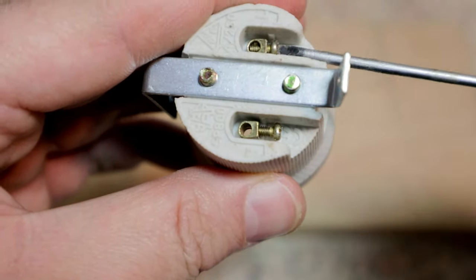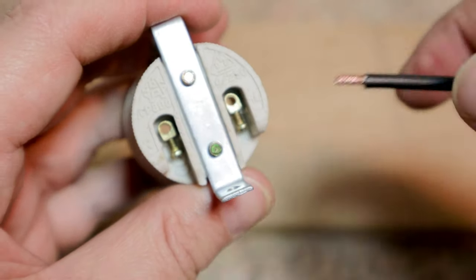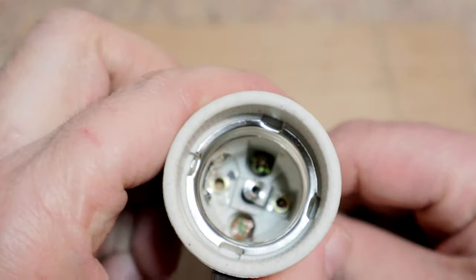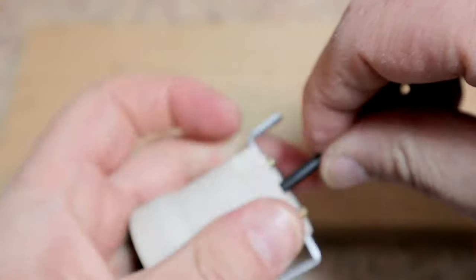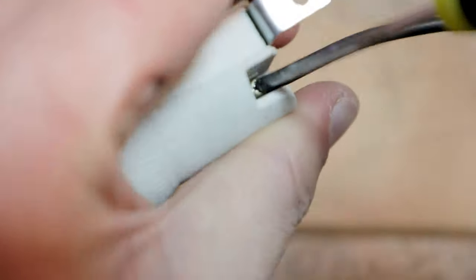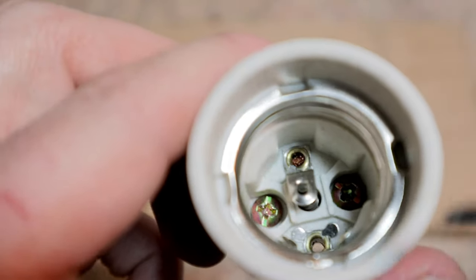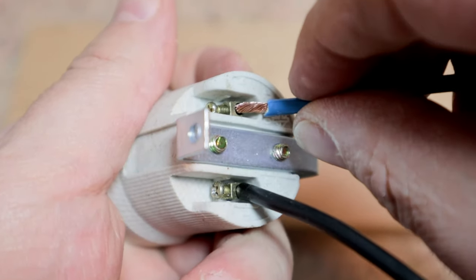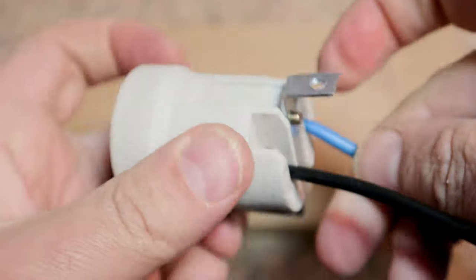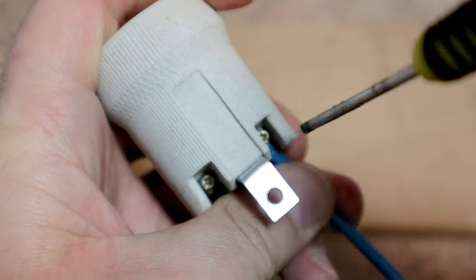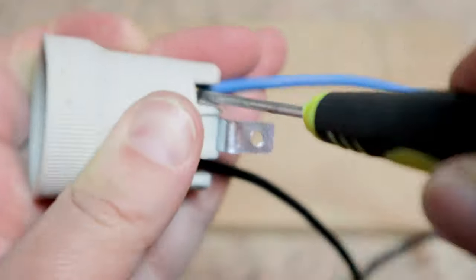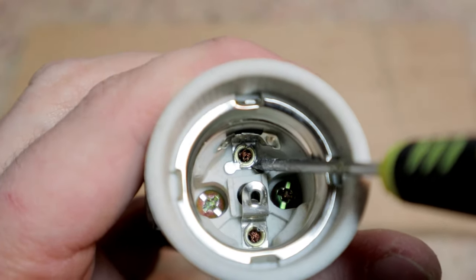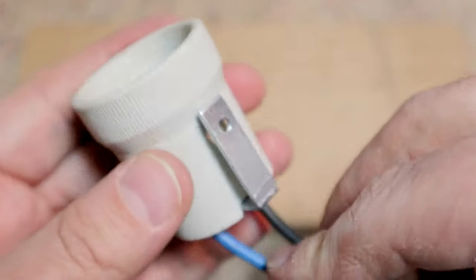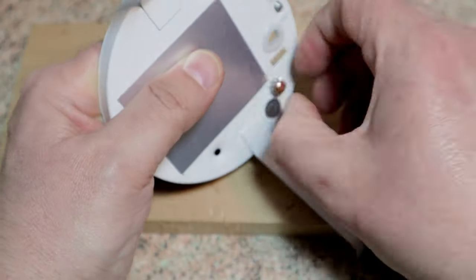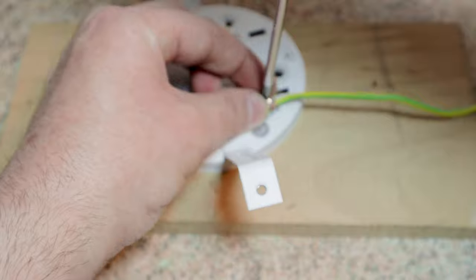I insert the phase cable and the neutral one in the respective terminals and tighten the screws. Usually near the terminal it is indicated whether it is the phase or neutral one. But in any case the phase terminal is the one that connects to the central contact of the bulb. I connect the earth cable to the connection prepared by the manufacturer on the base of the ceiling light. Even if the old system does not include the earth cable, I prepare it anyway.